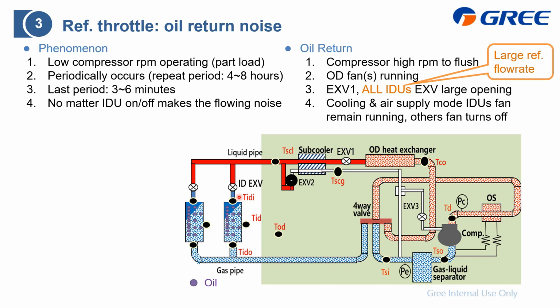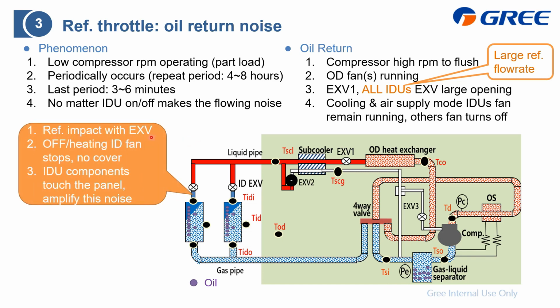So I will show you how the oil flows inside the oil return period, just like this. You can find it. We make the refrigerant flush this oil back to the gas liquid separator. Then it can be supplied to the compressor for lubrication. So the reason why this noise happens is this one: refrigerant impacts the EXV. For the off indoor unit and the heating indoor unit, the fan is turned off, which means there is no other noise to cover this noise. Then it becomes significant. And the last is that if these components touch the panel, it will amplify this noise.